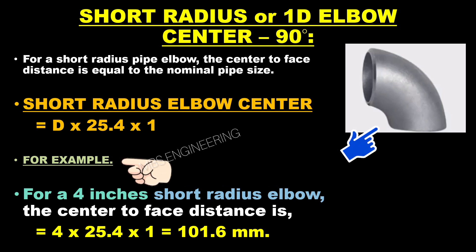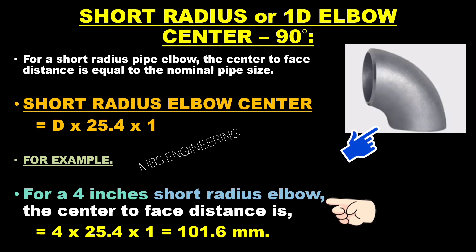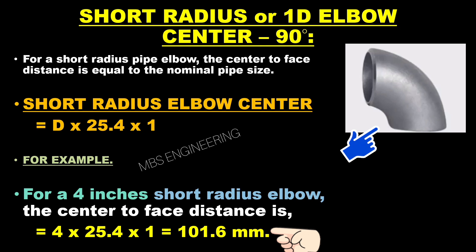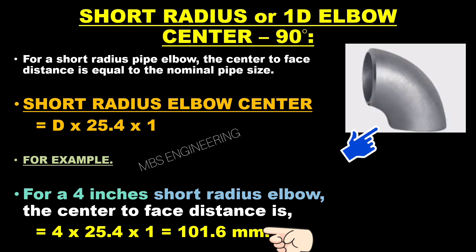For a 4-inch short radius elbow, the center-to-face distance is calculated as: 4 × 25.4 × 1. Therefore, the center-to-face distance for a 4-inch short radius elbow is 101.6 millimeters.